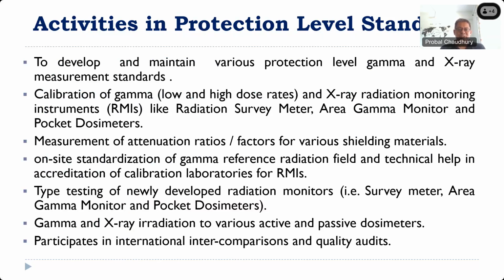Now coming to activities at the protection level. As I mentioned, we have lots of protection level equipment which is used for different applications. So we develop and maintain various protection level gamma measuring standards, and calibration of gamma monitors of different ranges, low range as well as high range dosimeters, and X-ray radiation monitoring instruments like radiation survey meters, area gamma monitors, and pocket dosimeters. Pocket dosimeters are personal monitoring devices which can give you an instant reading of how much dose you have consumed while carrying out a particular task. All these dosimeters are calibrated in the protection level standards group.